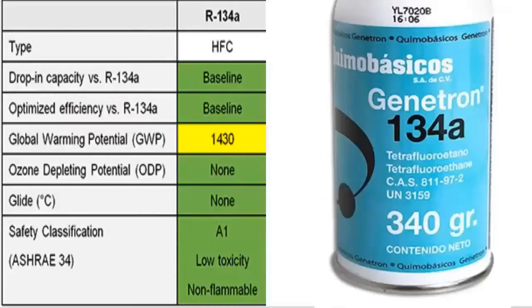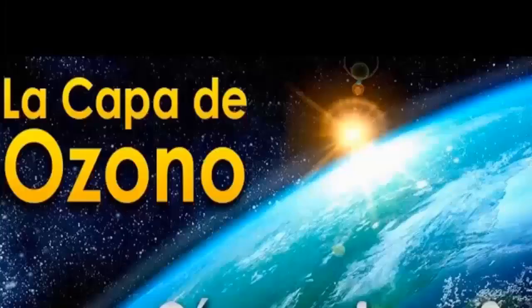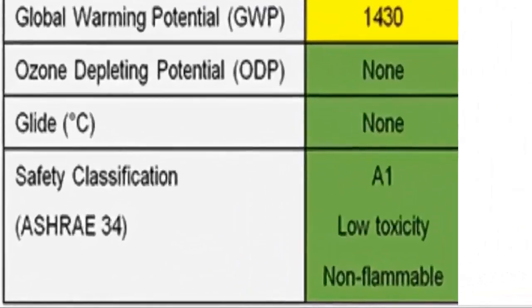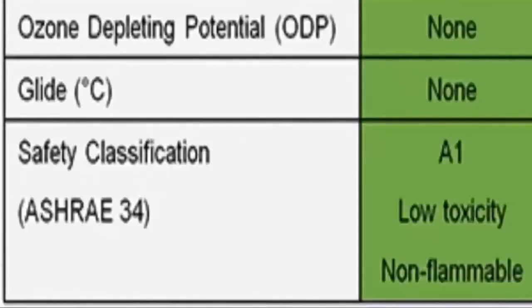These are the main features of R-134A that you should know about. 1. R-134A does not harm the ozone layer. 2. R-134A is not flammable, classified as A1. 3. R-134A is non-toxic, classified as lower toxicity.